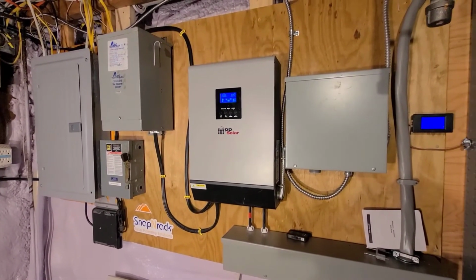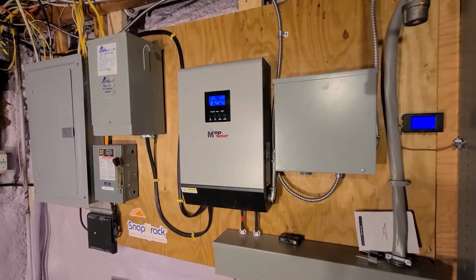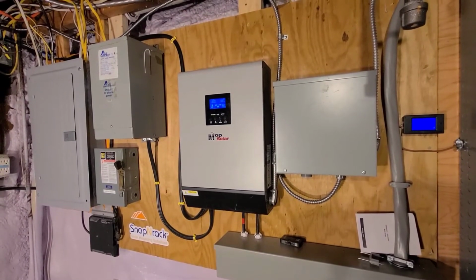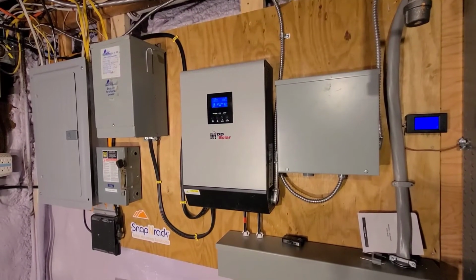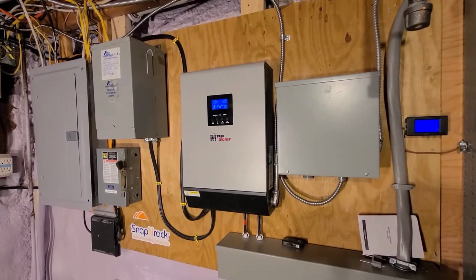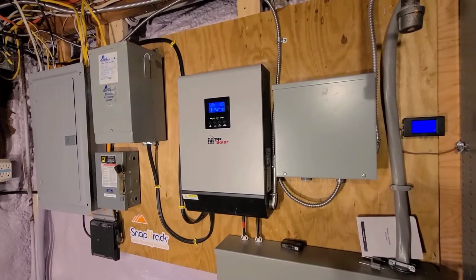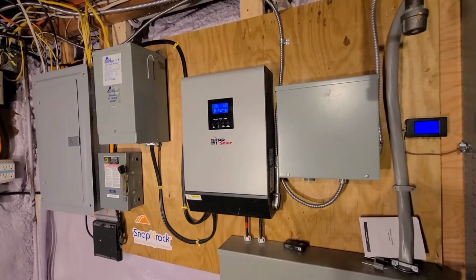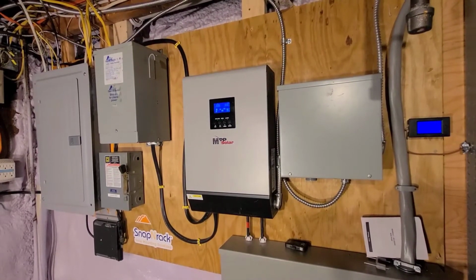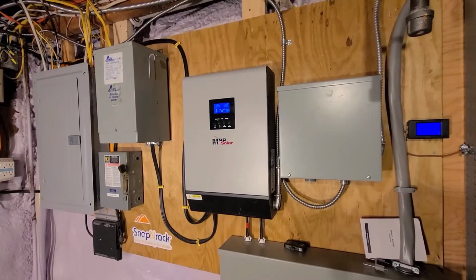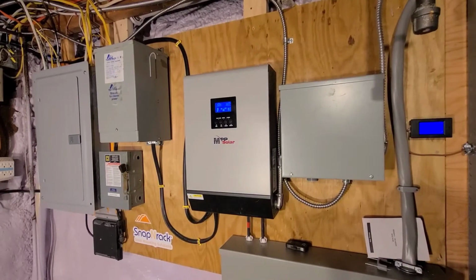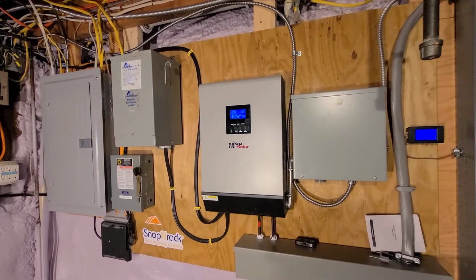Also, one thing I found out the hard way is that the PV side is not galvanically isolated from the AC side. So what that means is that when there's power on the AC side, there's also power on the PV input. And I did find that out the hard way. I double checked with MPP Solar and they confirmed it.